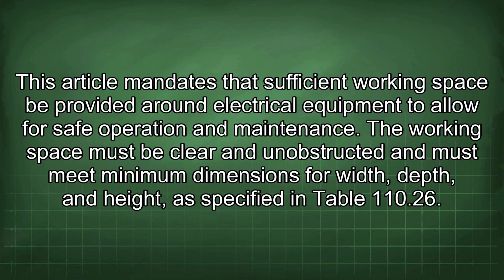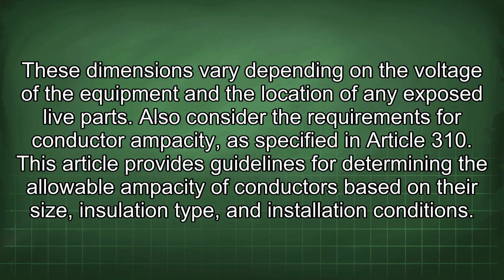This article mandates that sufficient working space be provided around electrical equipment to allow for safe operation and maintenance. The working space must be clear and unobstructed and must meet minimum dimensions for width, depth, and height, as specified in Table 110.26. These dimensions vary depending on the voltage of the equipment and the location of any exposed live parts. Also consider the requirements for conductor ampacity as specified in Article 310. This article provides guidelines for determining the allowable ampacity of conductors based on their size, insulation type, and installation conditions.